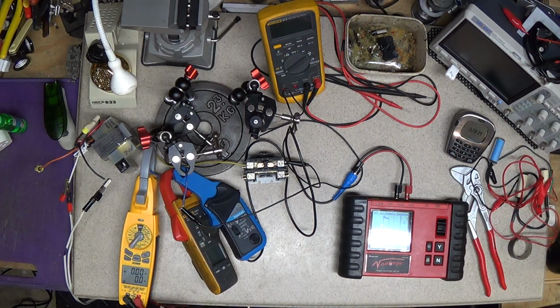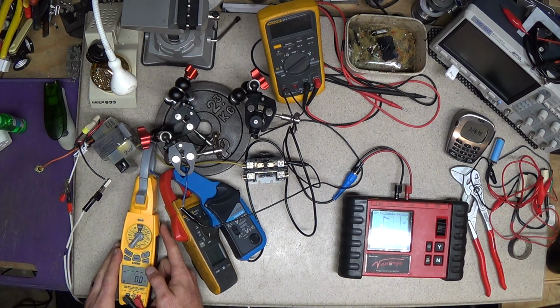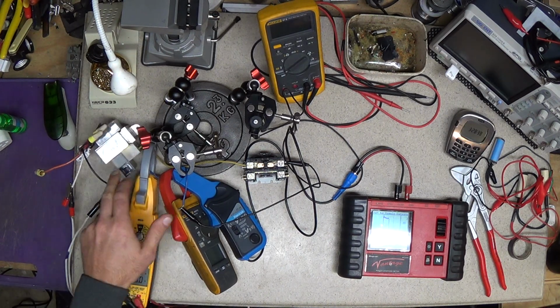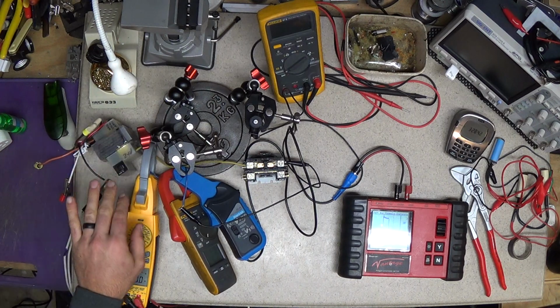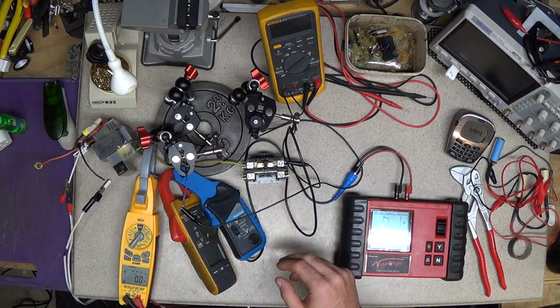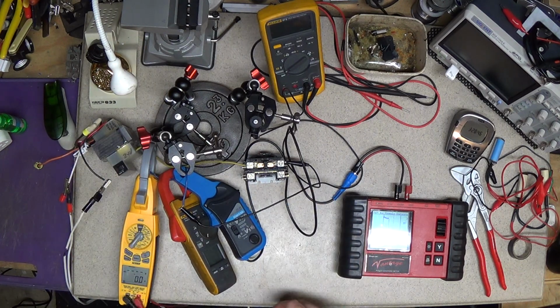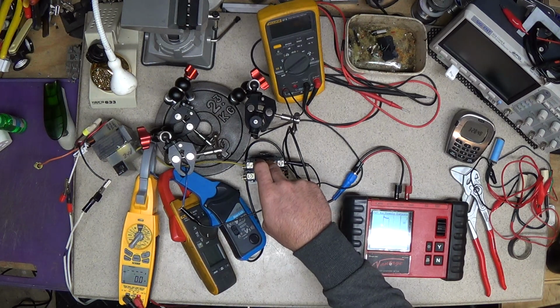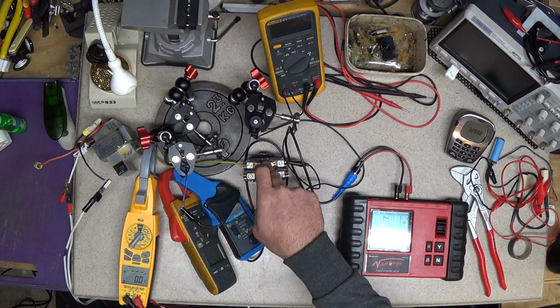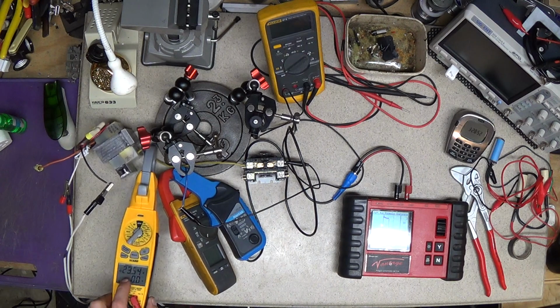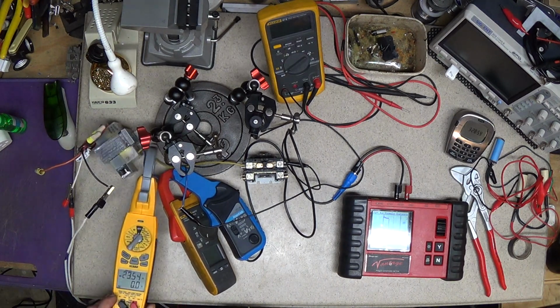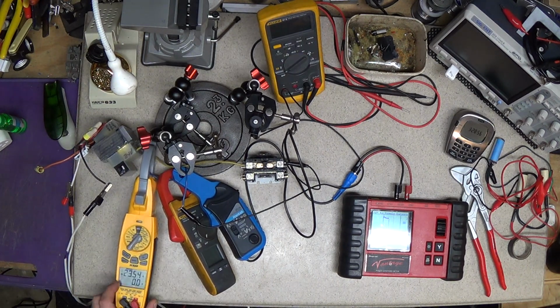So out of curiosity, let's try the breaker again. Now keep in mind this is warm now, so it's probably going to trip quicker than it would cold. But I'm going to reset the inrush and just try it now. Okay, so we had 23.5 on inrush.